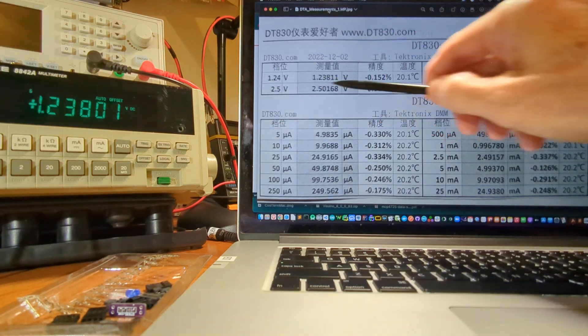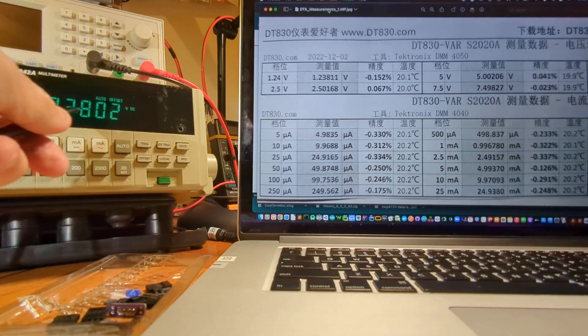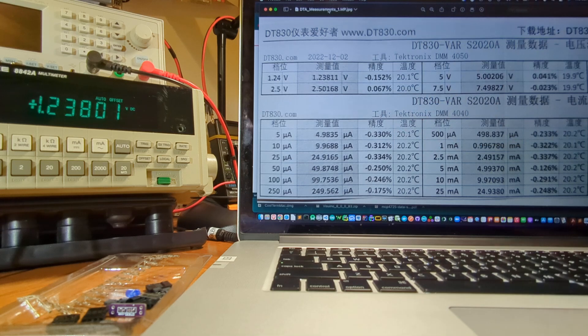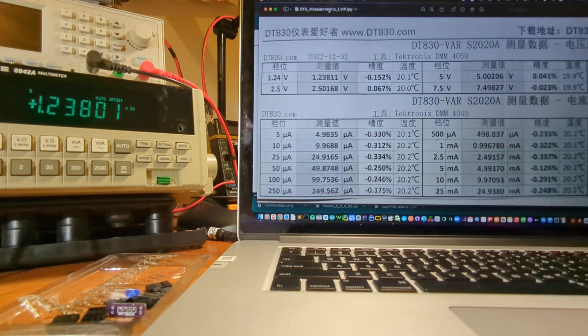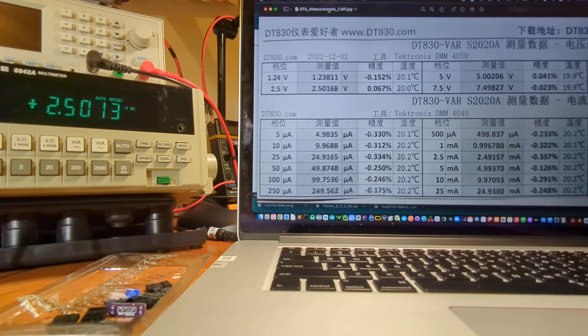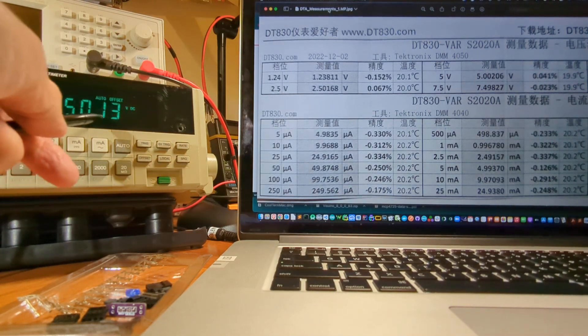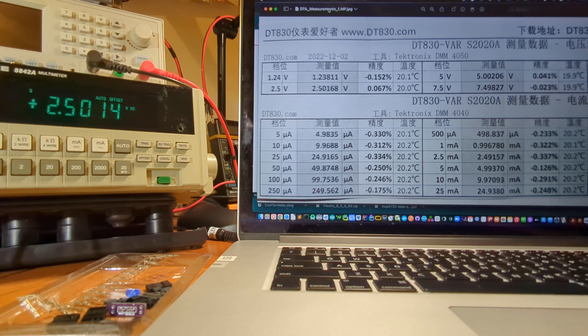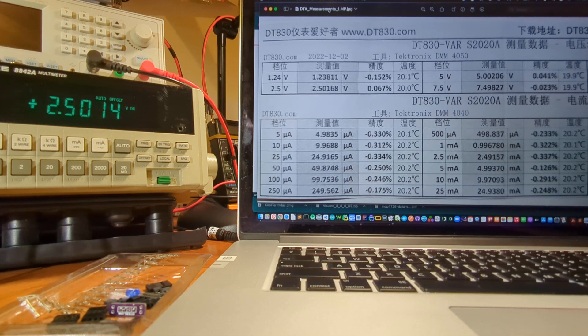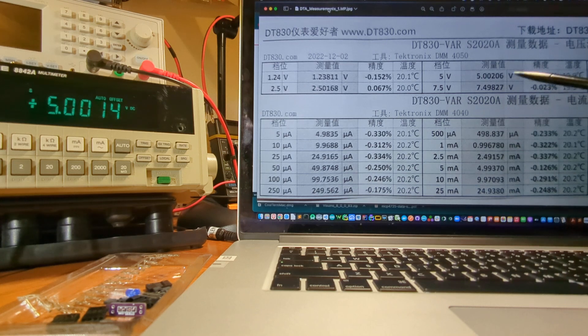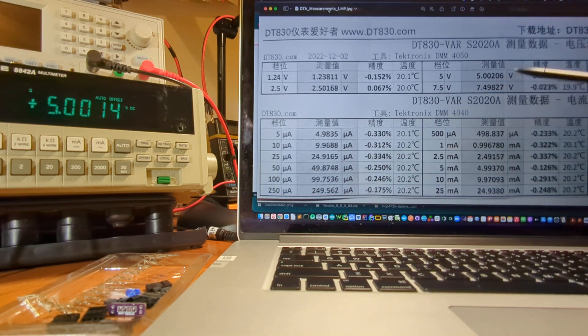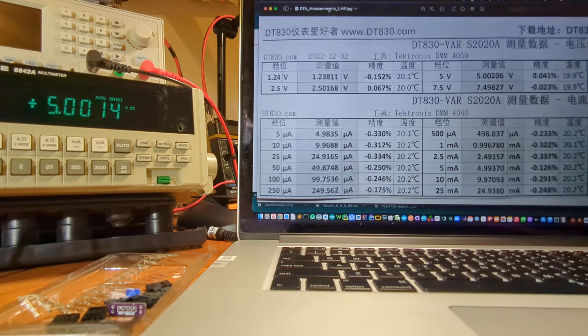So now we're on this row here. It says to expect 1.238 and we're getting 1.23802. We're off by a tenth of a millivolt compared to what they would expect. That's pretty good. Going to the next one, 2.5 volt range. 2.50168, I'm getting 2.5013 or 2.5014. So off by three tenths of a millivolt, four tenths of a millivolt, something like that.